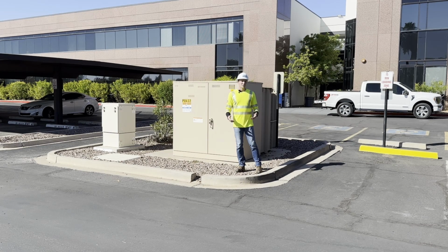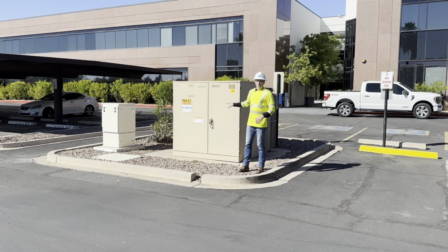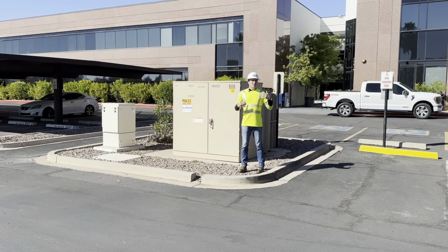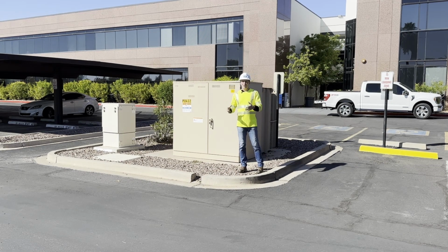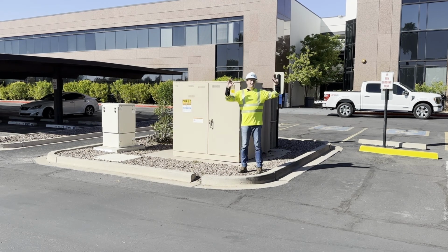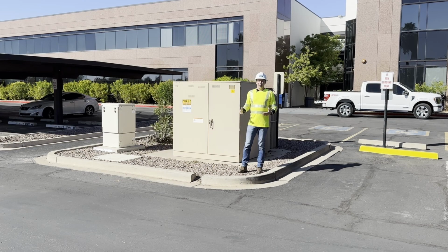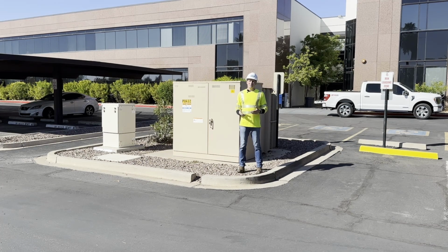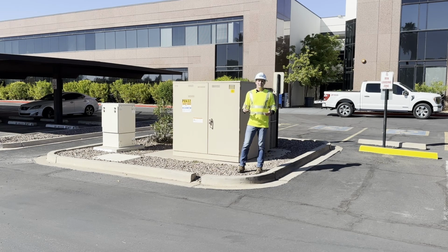This is really important to know, because if you're in a very rural area, or served by a small municipal utility or co-op in the middle of nowhere, they might not actually have a Y transformer. That's critical to know before starting your EV charging project, so your engineer of record knows they'll have to do extra work to accommodate the fact that the utility won't be providing a neutral.